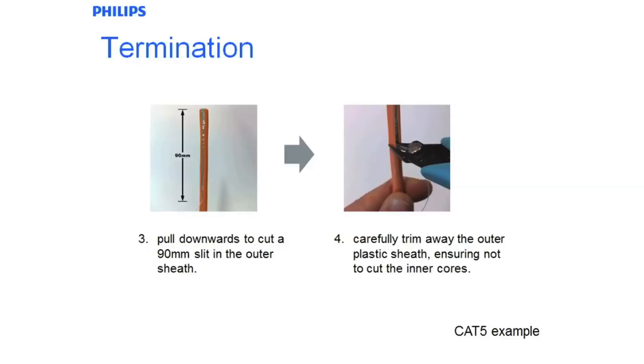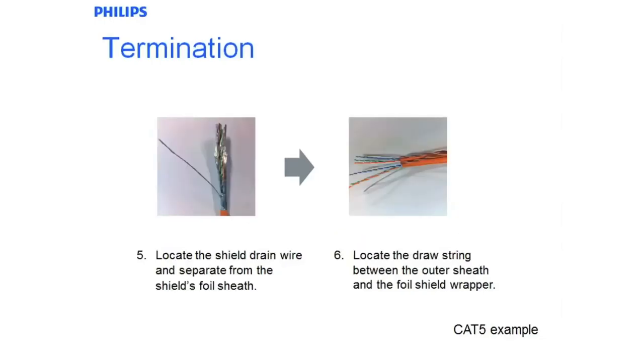Locate the shield drain wire and separate from the foil sheath. The drain wire is the shield termination. The foil that goes around it gives 100% shielding of the inner conductors. This increases the noise immunity of the network.